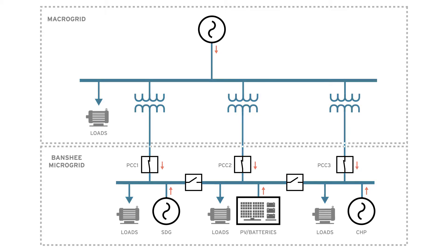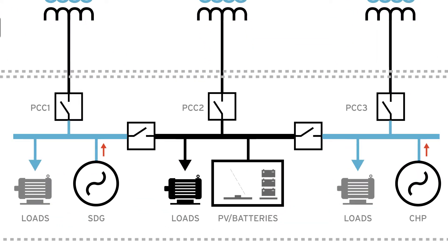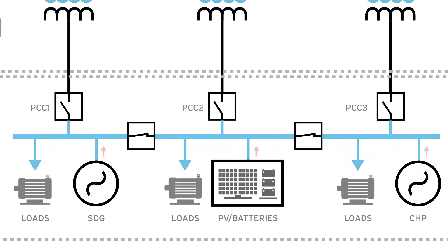As we are evaluating multiple vendors, it was critical to develop a test sequence which is equal for everyone. We started with the microgrid connected to the grid, then the next phase is called planned islanding. After this period we reconnect back to grid, then we have unintentional islanding. We reconnect to the grid and this way we conclude our test sequence.